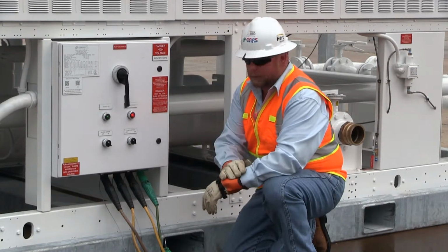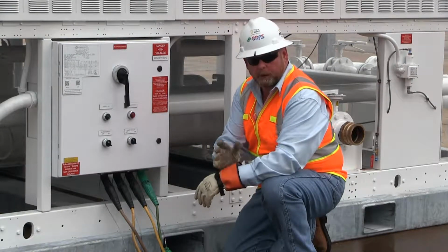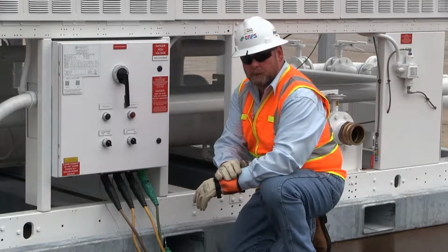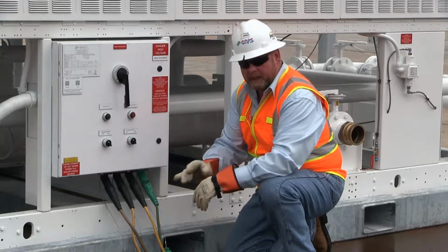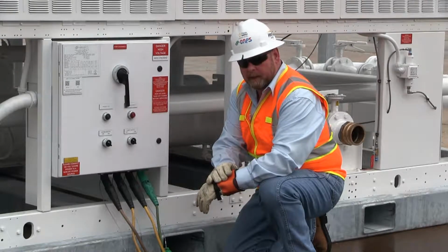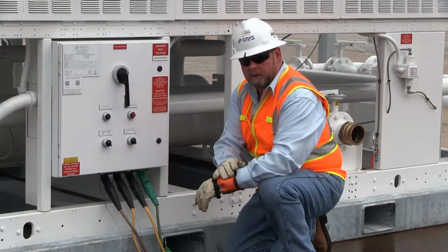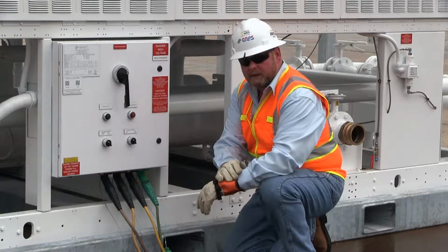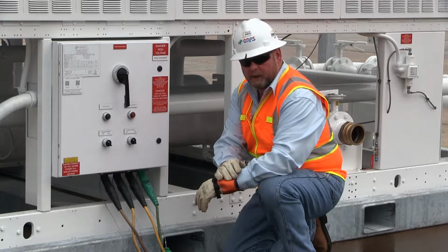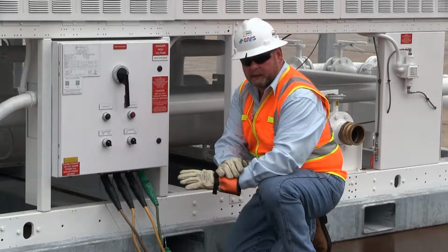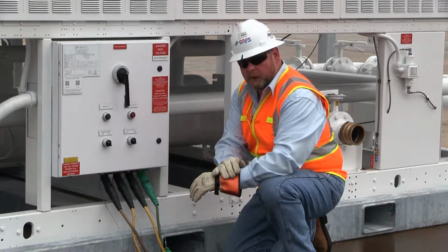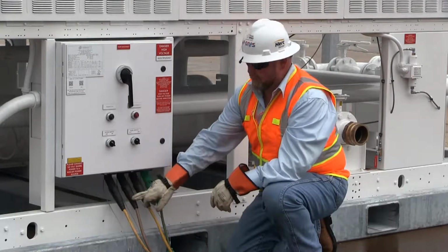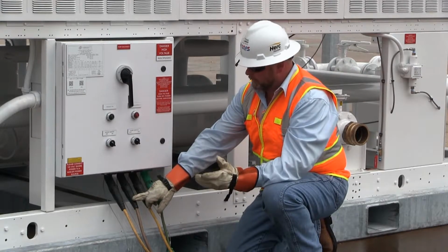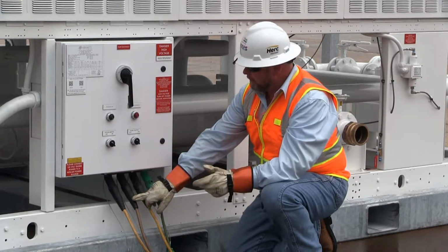So we'll kill the power to the machine completely. We'll lock and tag out our main power source, and then we're going to reverse two leads on the incoming power. Please note that you never change the incoming leads on the cam locks while they're energized. They must be completely de-energized and the load completely locked out. Okay, we've reversed L1 and L2 here to get our phase correct. Now we're going to re-energize the power.